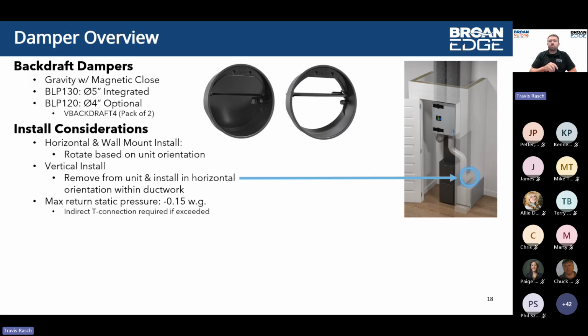If we go to that unique vertical install, and you're using the BLP 130 models, you're going to have to remove those 5-inch integrated dampers. They just slide out of the port, and we're going to have to put them in a horizontal orientation. Whether that's in ducts, or maybe somewhere else along the way, because we're trying to use gravity as our friend, we have to have those dampers in a horizontal orientation.